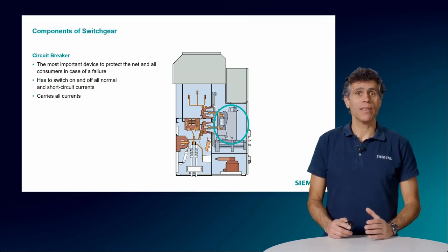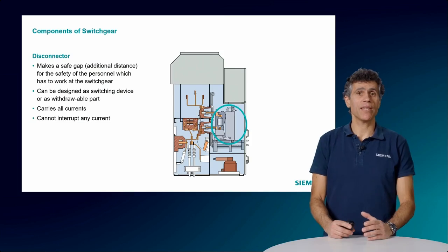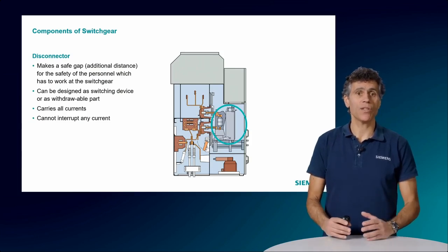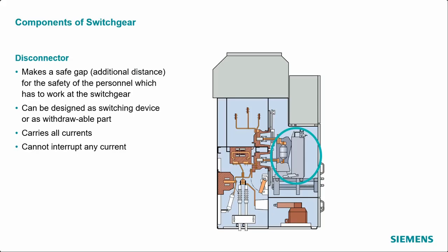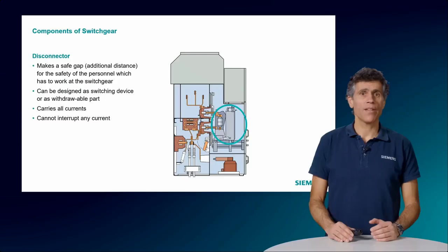As mentioned before, sometimes other devices can be used instead of a circuit breaker when the duty is not so demanding or for other specific duties. One of those devices is the disconnector. If it's a simple disconnector, it's also called an isolator because that's all it does. It isolates the next section. As it can't break currents, it can only be inserted or removed when no current is flowing. A disconnector can also be designed to switch operating currents on and off, and in that case it's called a switch disconnector. The common thing to both is that they cannot switch fault currents.